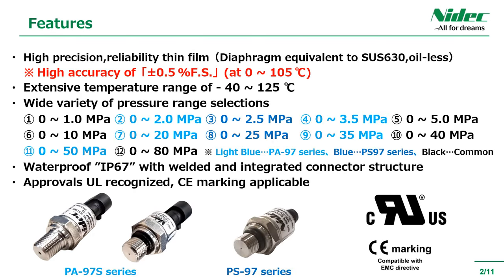These are the features. A thin film element and a diaphragm equivalent to SUS630 are used, and the overall accuracy is 0.5% full-scale, boasting extremely high precision and high reliability. The operating temperature is compatible with an extensive range from minus 40 degrees Celsius to 125 degrees Celsius, and the pressure range covers a wide variety of medium and high pressure ranges from 1 MPa to 80 MPa.